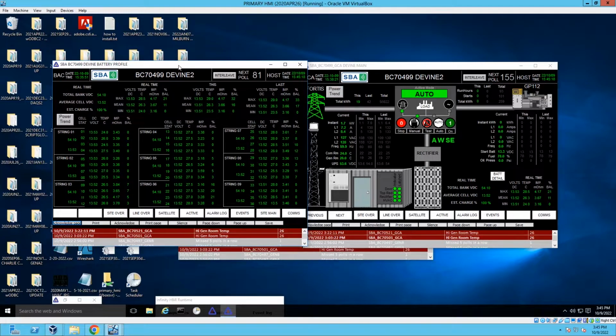As usual, we have the last communication with the site in the top left corner, followed by the site ID and name in the top center position, and the interleave button and indicator, and finally by the current host time. Across the bottom, the alarm log and standard navigation buttons are present. Our real-time values here are mirrored on our site overview screen, which include real-time values for total bank voltage, average cell voltage, and estimated state of charge.